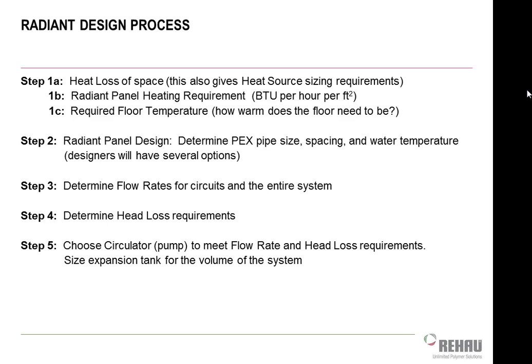I'll use that to size up my panels or my floor tubing. How much tubing do I need in the floor, and how far should it be spaced, based on what the load of that particular space is going to be. That can also determine my pipe size. Once I have all that, so I know my pipe size and the flows and water temperature that I need, I can use that to size my pumps and all the way down the line, just like I would on a regular hydronic system. So nothing's really different there other than the fact that I'm putting tubing in the ground.